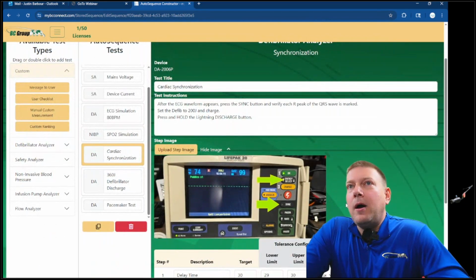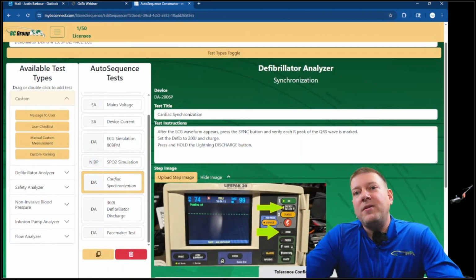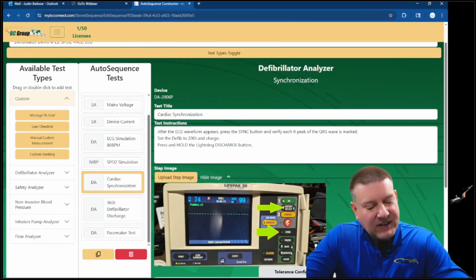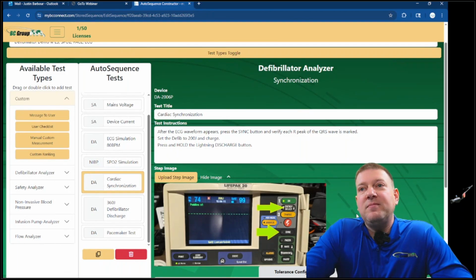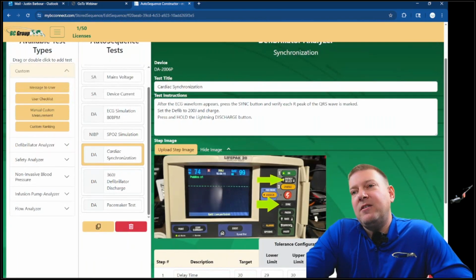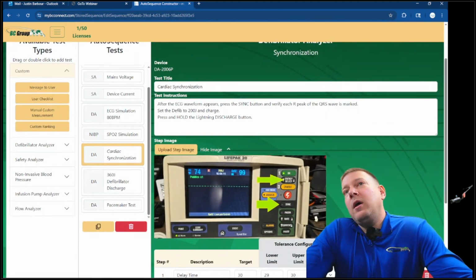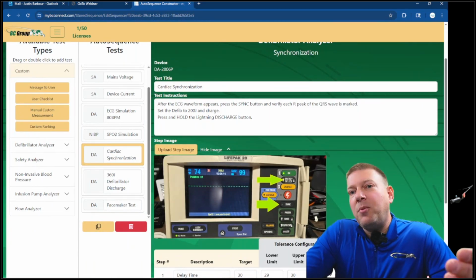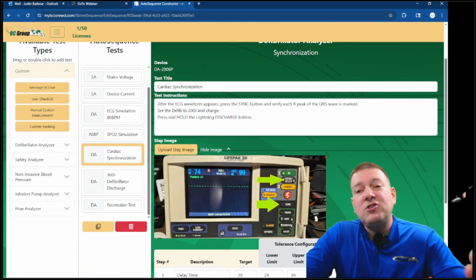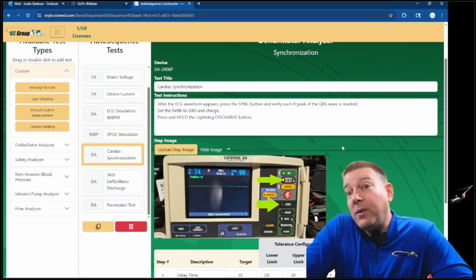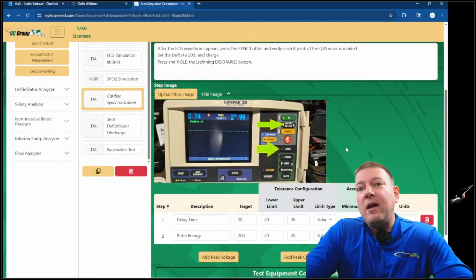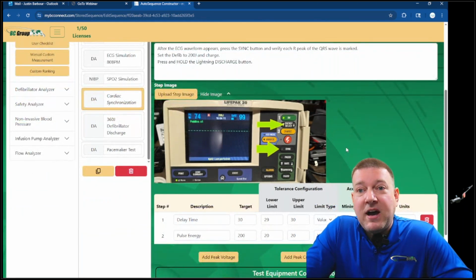So over here, we're on cardiac sync. Now this cardiac sync is one of those things that technicians, they always mess up because they don't even know the standard for what they're supposed to be working with. With cardiac sync, it's supposed to receive a discharge within 60 milliseconds of the R wave pulse. And because of that, most people don't know that, and they're just getting a timing, they're recording it down. They don't even know if it's a pass or fail.